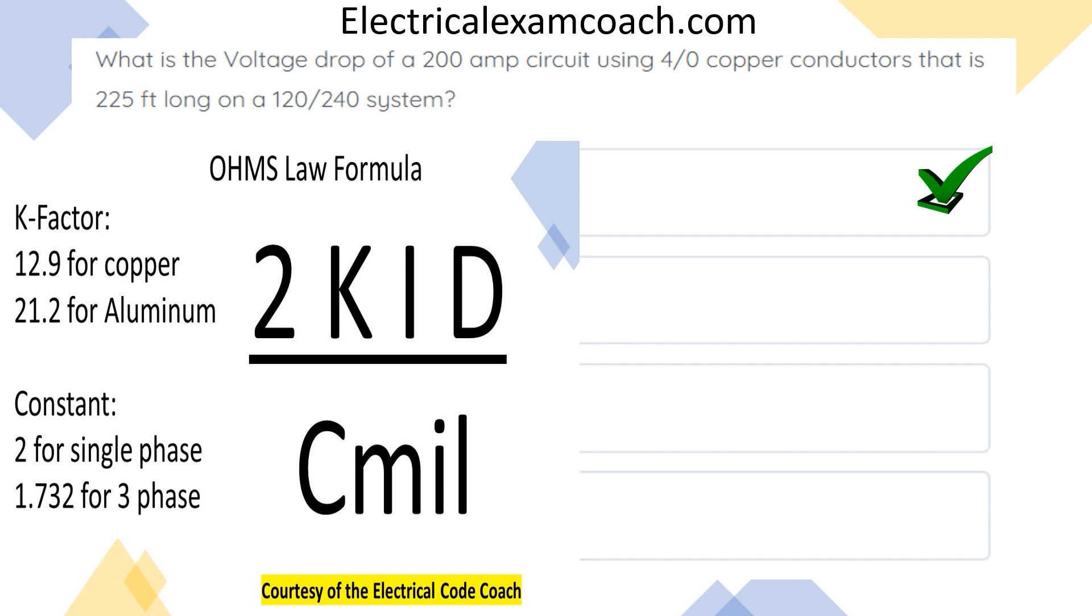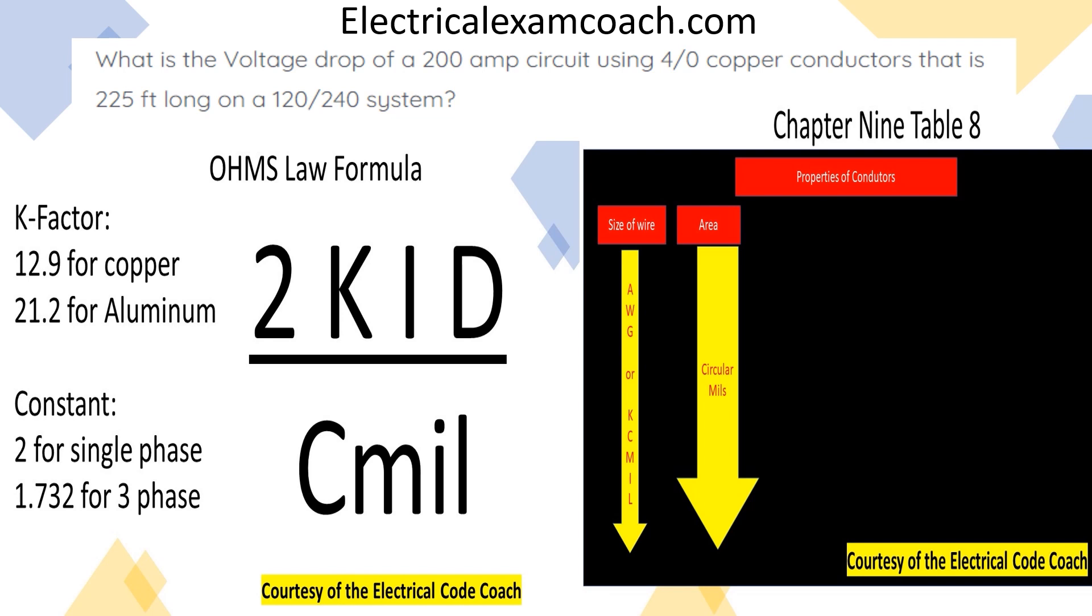For this one, we're going to use our Ohm's Law formula, two kid over C mils. We're going to have two as our constant. Our K factor is going to be 12.9 this time because it's copper. And then we're going to have our current and our distance divided by the C mils. In order to get that information, we're going to head over to chapter nine, table eight. We're going to start on the left-hand side until we find our conductor. Then we're going to come over and we're going to get our C mils. After we bear out all our math, and this is what I love about formulas. Just plug in what you know, and then spit out the answer. Two multiplied by 12.9, multiplied by 200, multiplied by 225, divided by the circular mils of a 4-aught copper conductor is going to equal 5.48676, and it continues on. We're going to round up to 5.5 and call it a day. Let's get to it.